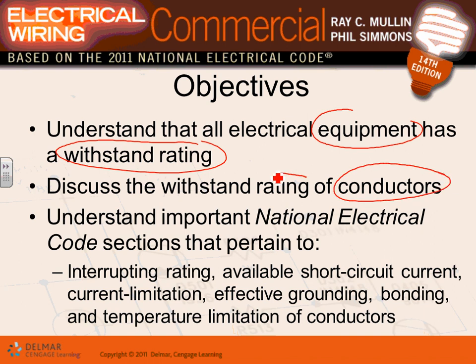Conductors also have a withstand rating. A withstand rating is when you have a short circuit in the conductor, the conductor sits there and holds it. It's getting hotter and hotter. There's a certain limit, typically measured in cycles. After a certain number of cycles, you know what's going to happen? That conductor will completely burn. That's called the withstand rating.